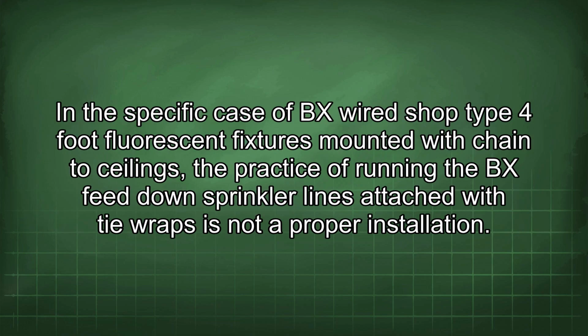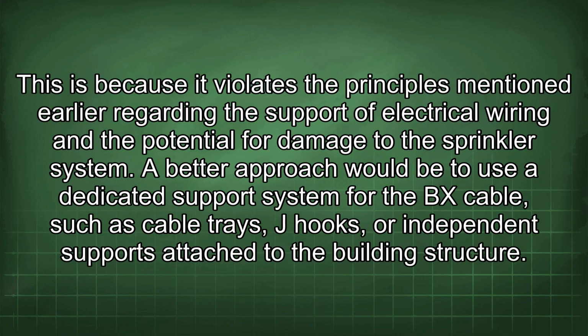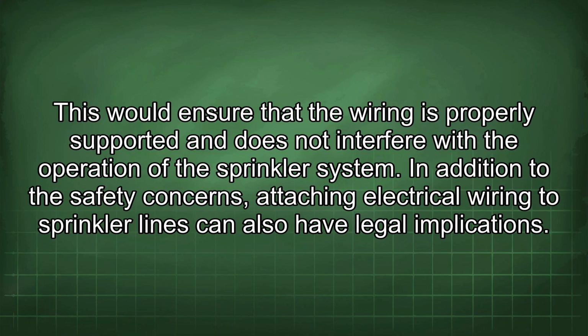In the specific case of BX-wired shop type 4-foot fluorescent fixtures mounted with chain to ceilings, the practice of running the BX feed down sprinkler lines attached with tie wraps is not a proper installation. This is because it violates the principles mentioned earlier regarding the support of electrical wiring and the potential for damage to the sprinkler system. A better approach would be to use a dedicated support system for the BX cable, such as cable trays, J-hooks, or independent supports attached to the building structure. This would ensure that the wiring is properly supported and does not interfere with the operation of the sprinkler system.